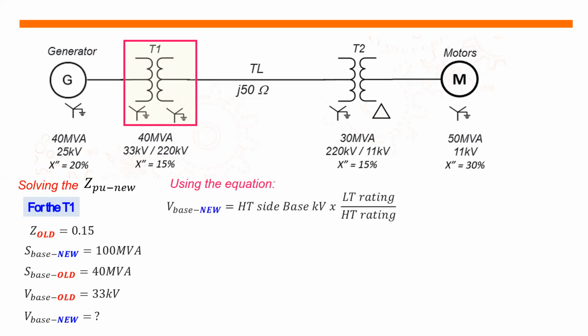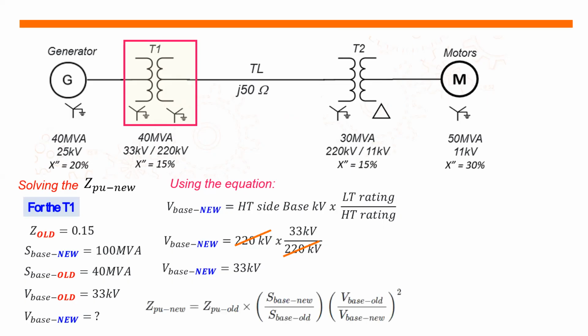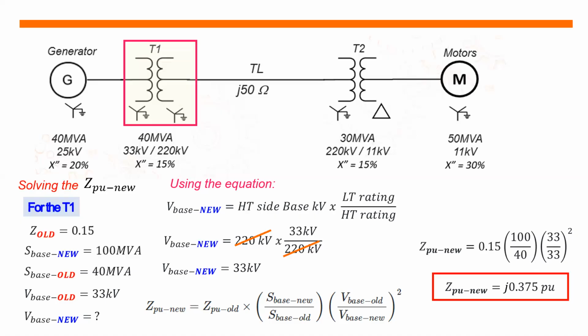So using the equation to get the new base voltage of the transformer, the high tension side base kV multiplied by the low tension side rating divided by the high tension side rating. So in the high tension side, our base kV is 220 kV multiplied by the 33 kV over 220 kV. Then we will cancel the 220 and we will get the new base voltage of the transformer as 33 kV. Then now all the givens are complete. Then we can substitute these values to our equation to get the new per unit impedance. And we will get the new per unit impedance is equal to j0.375 per unit.